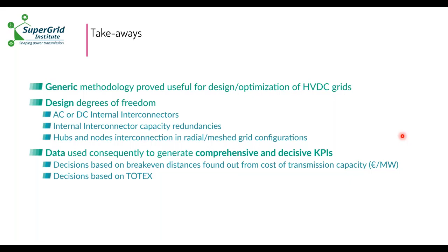But once you have decided what is the best economically feasible architecture for the system, then you need to study how you protect the system against any disturbance. And that will also impact a little bit this first adequacy, because we will add some more components, which are the protection components, DCCBs and switches, for example. So the protection of an MTDC network will take part since the occurrence of a fault, let's say a short circuit on a line.